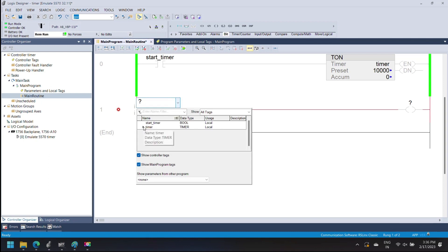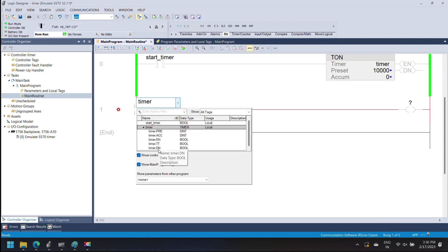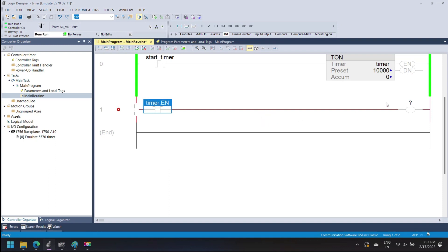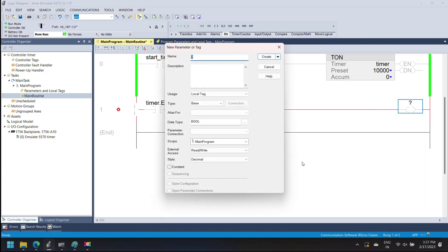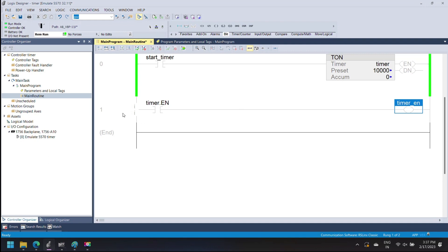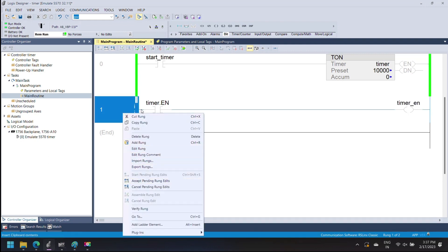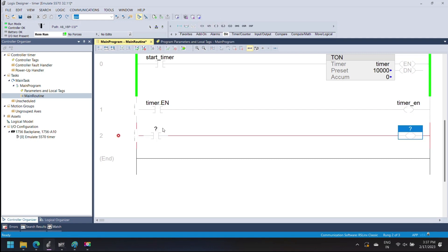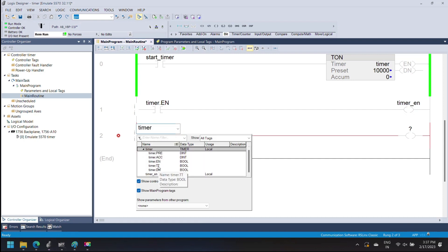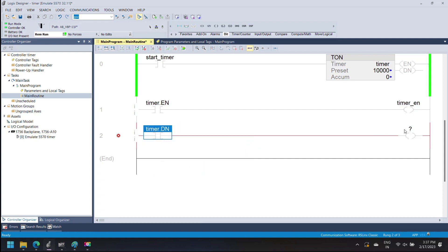I am adding a new rung and using the timer enable bit. The enable bit contains the rung condition when the instruction was last executed — data type bool. In this rung I am adding the timer done bit. The timer done bit is set when the timer accumulator is equal to the timer preset value. When the timer done bit is set to true, the timer operation is completed.